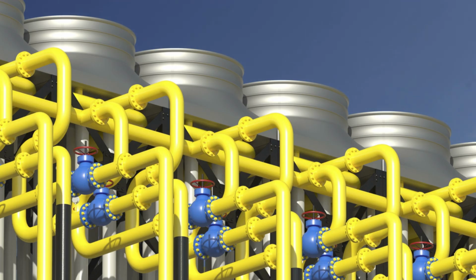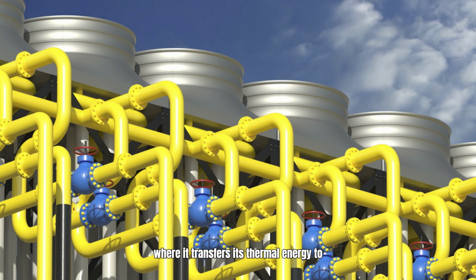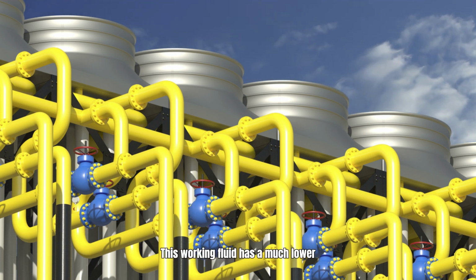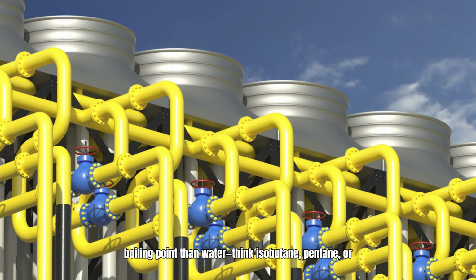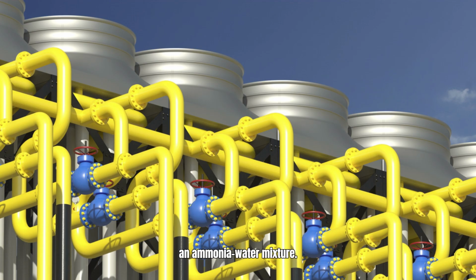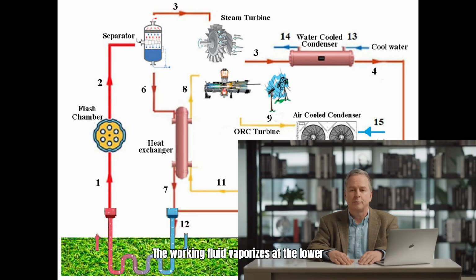Binary plants changed the game by making electricity generation possible at temperatures as low as 70 to 80 degrees Celsius. Here's how it works: the geothermal fluid, the primary fluid, never touches the turbine. Instead, it flows through a heat exchanger where it transfers its thermal energy to a secondary working fluid. This working fluid has a much lower boiling point than water, think isobutane, pentane, or an ammonia-water mixture. It vaporizes at the lower temperature, drives the turbine to generate electricity, then gets condensed and recycled in a completely closed loop. The geothermal water, meanwhile, is sent back underground.